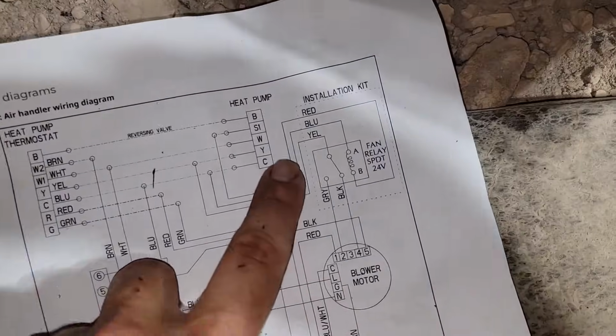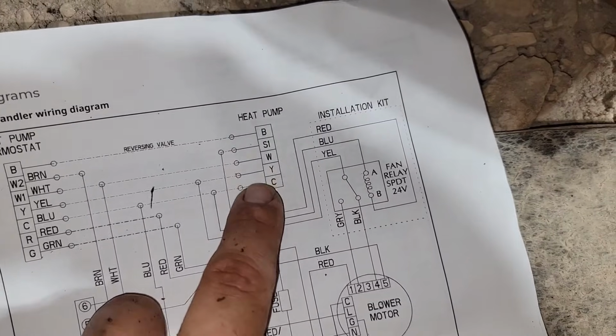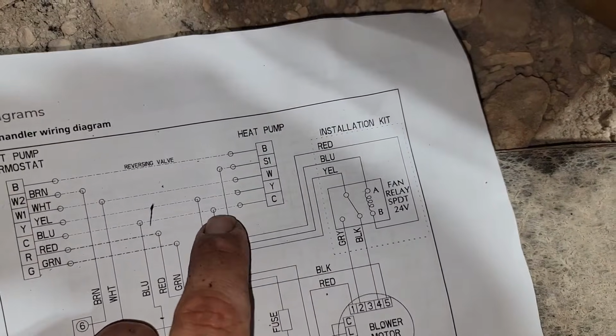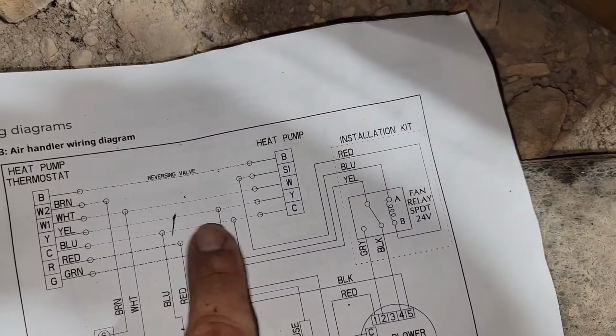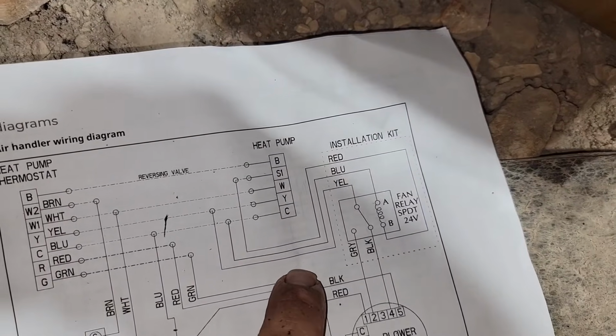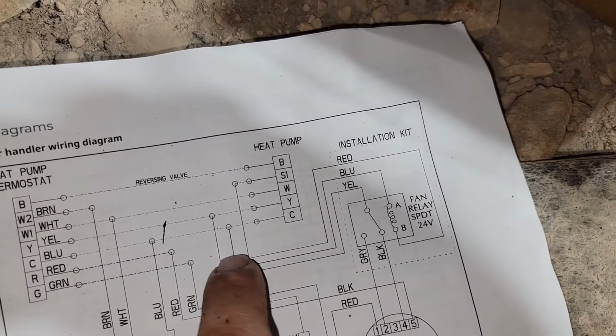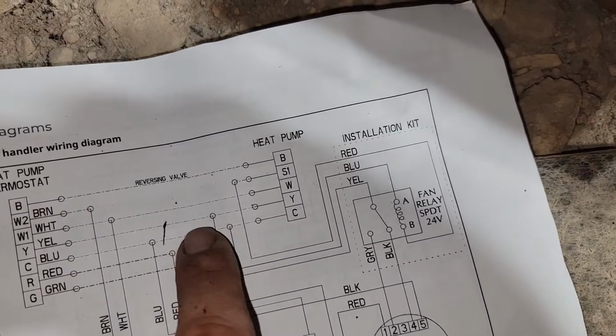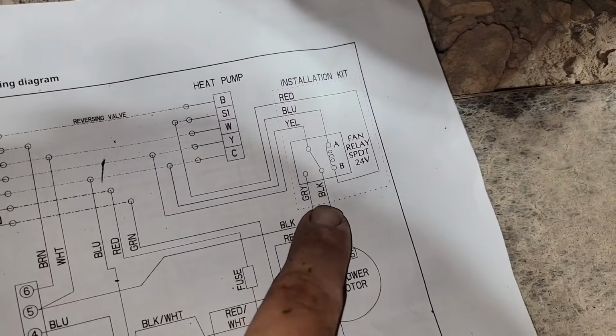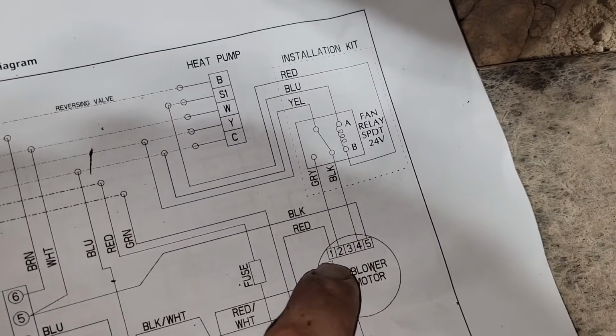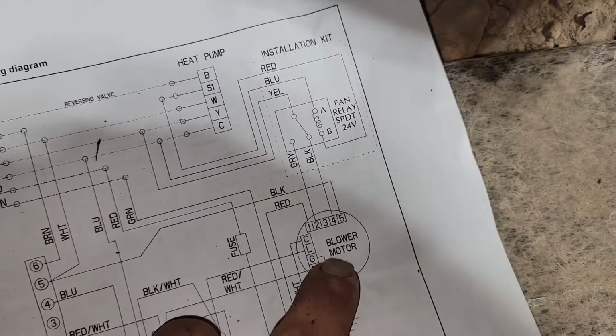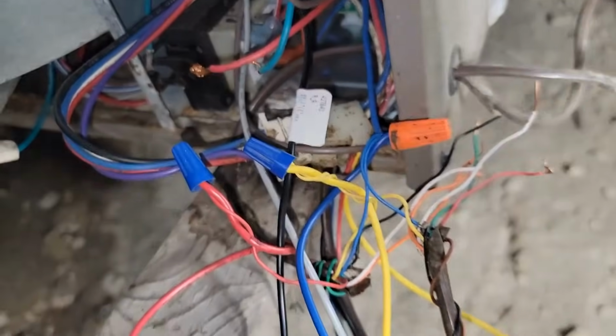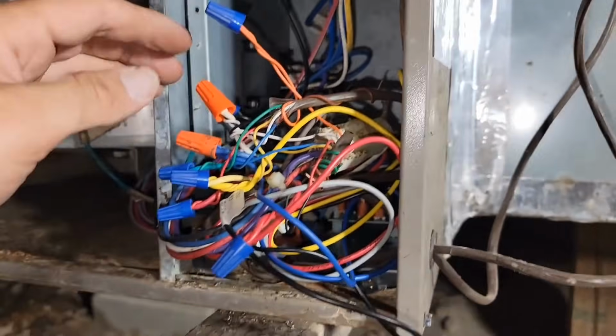Let me show you that here. Red wire goes to S1, blue wire goes to the common, okay, from the common to the common, and then the yellow wire went to the cooling call, and then 2 more wires, black and gray, and they go to 2 and 4. They go to the blower motor. All right, now I'll wire up the rest of the unit and show you that if you need to see it. All right, I'm gonna go over the rest of the wiring.